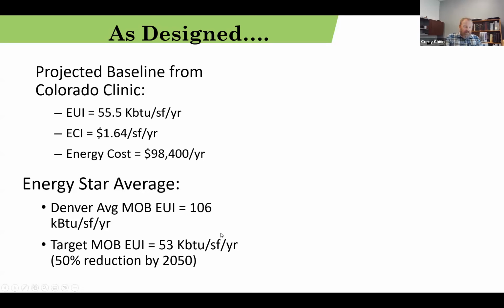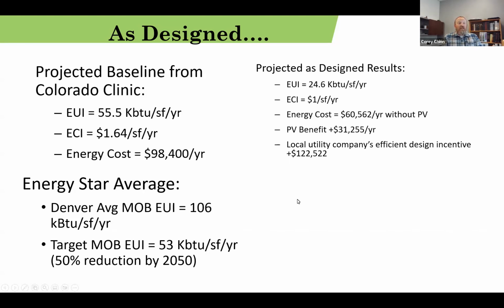To put this in perspective, Colorado's average EUI for a medical office building is 106 kBTU per square foot per year. Their target for 2050 for 50% energy reductions is 53 kBTU per square foot per year. All right, our building was designed for an EUI of 24.6 kBTU per square foot per year and a cost index of $1 per square foot per year prior to the PV benefit. So we were looking at about $60,000 a year. And the PV benefit was going to give us an additional $30,000 a year. We did get $122,000 from the local utility, from Black Hills Energy. They were projected to give us $122,000. So these are projected results.